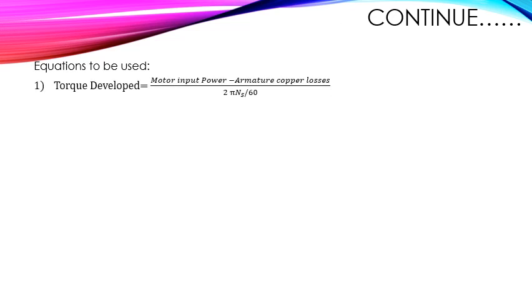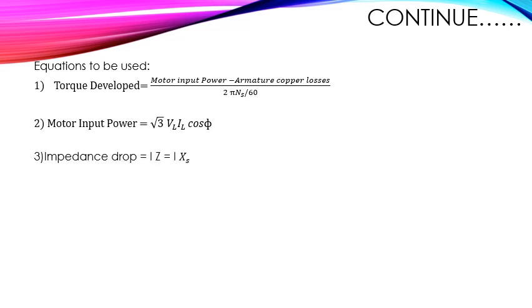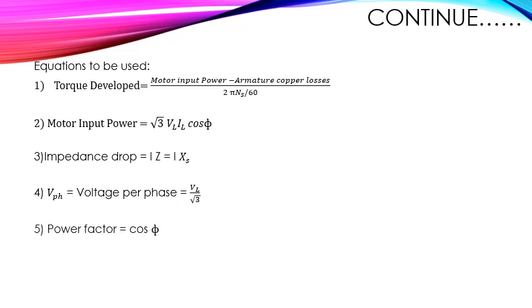We have to determine power input, power factor, and torque developed for an armature current of 250 A. Equations: torque developed = (motor input power − armature copper loss) / (2π·ns / 60). Motor input power = √3 · VL · IL · cos φ. Impedance drop = I·Xs. Phase voltage Vph = VL / √3. Power factor = cos φ. Line induced EMF EL = √3 · Eph.